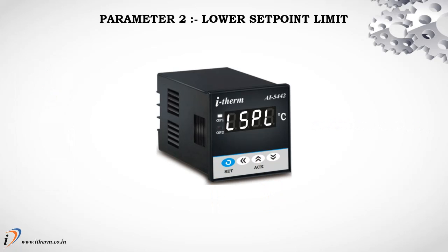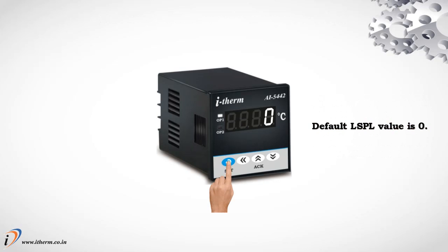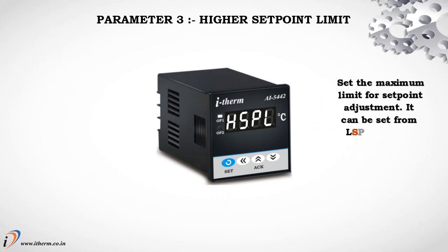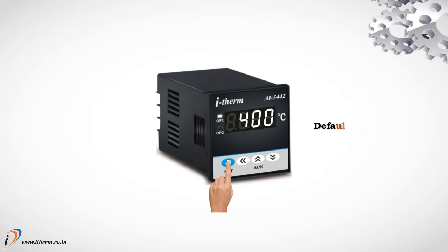Parameter 2. Lower set point limit. Set the minimum limit for set point adjustment. It can be set from minimum specified range of selected sensor to HSPL value. Default LSPL value is 0. Parameter 3. Higher set point limit. Set the maximum limit for set point adjustment. It can be set from LSPL value to maximum specified range of selected sensor. Default HSPL value is 400.